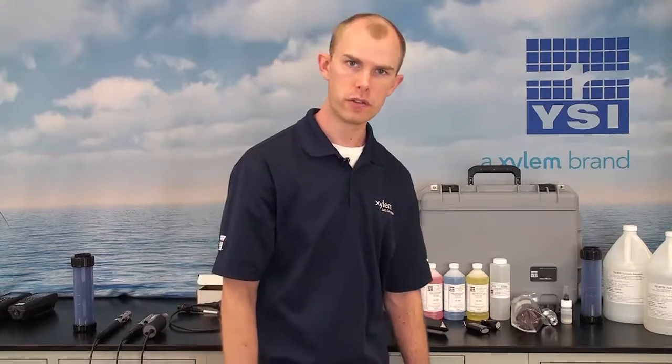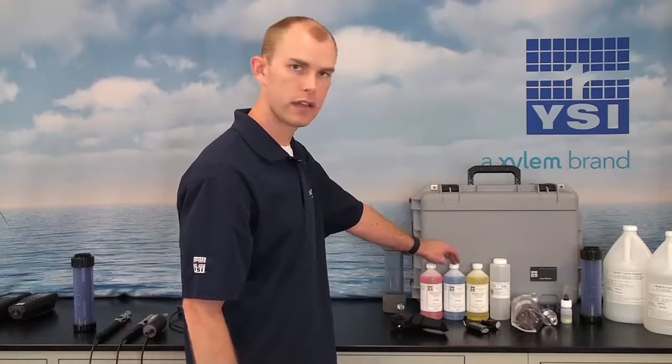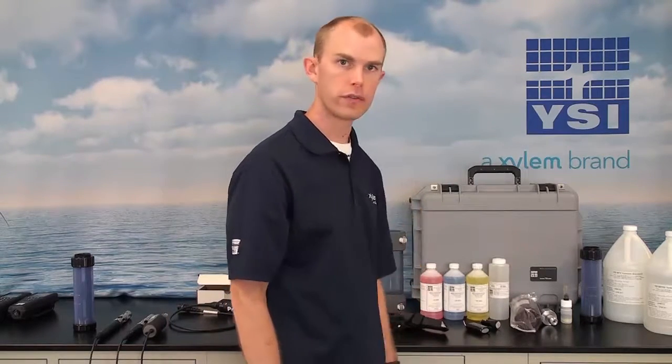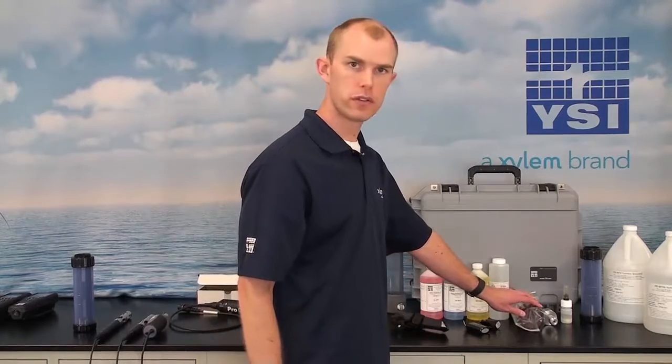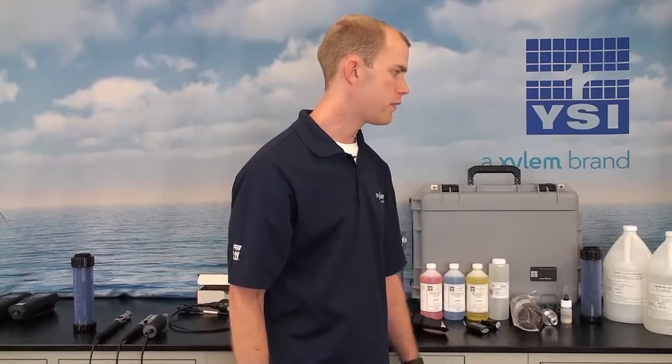The last step in putting together your ProDSS system is to consider the accessories available. We have different calibration solutions including pH 4, 7, and 10 buffers for calibrating pH, conductivity solutions ranging from 1,000 up to 100,000 standard, Zobell solution for calibrating the ORP sensor, and turbidity standards for calibrating the turbidity sensor.